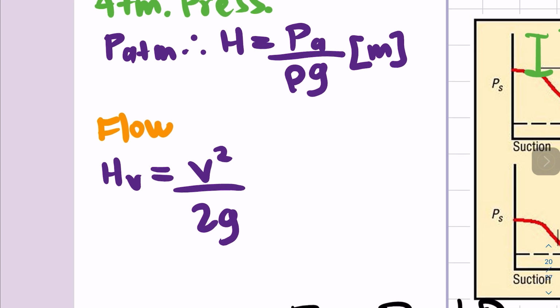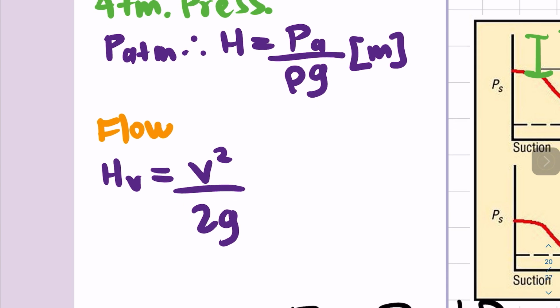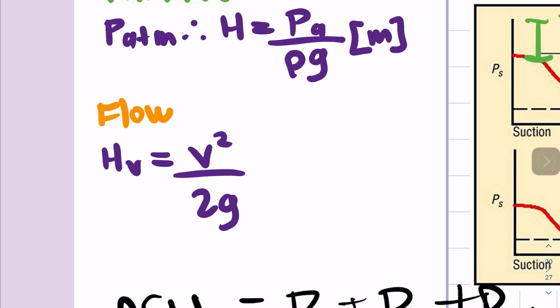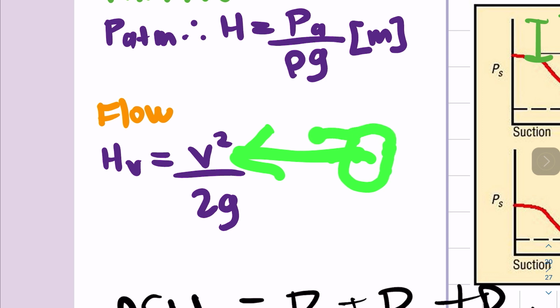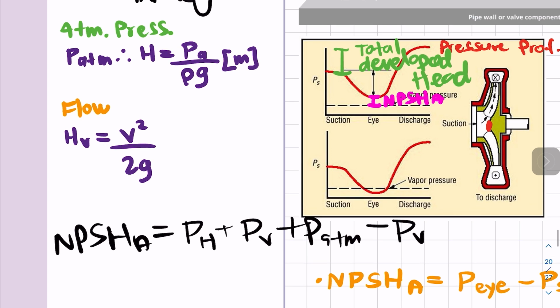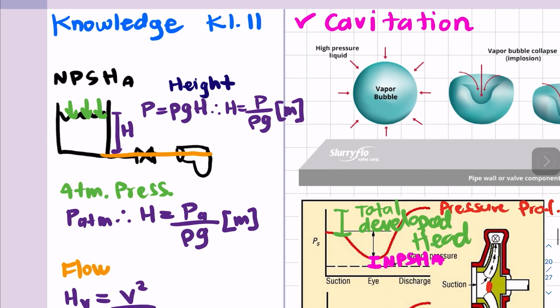But okay, I'll just jump into it. So we have the flow here, right? Remember that I said flow is going to be the kinetic energy. So in order to calculate it, our head, the height of the velocity, is going to be equal to the speed squared over 2 times gravity, because we only have this thing flowing in the pump, right? So net positive suction head available is going to be the velocity head, the pressure head, and the atmospheric pressure, right?